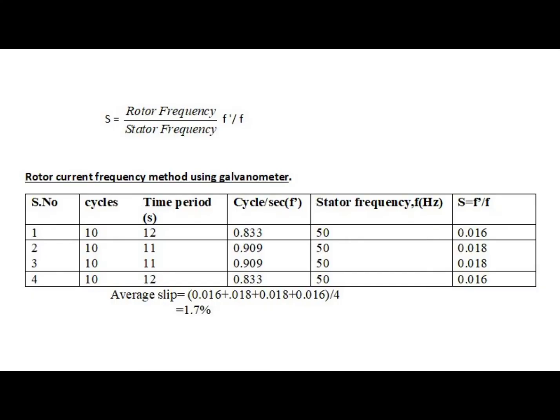We found the rotor current frequency by counting 10 cycles and noting down its time period. Then in order to find slip, we divided our rotor frequency by the stator frequency. The stator frequency is 50 Hz, so after putting our values, we found an average slip of 1.7%.